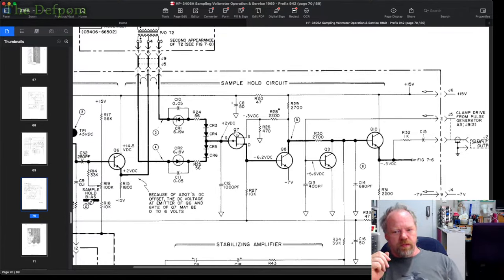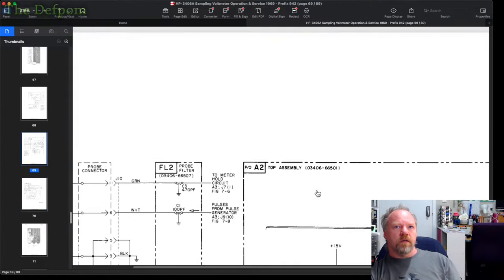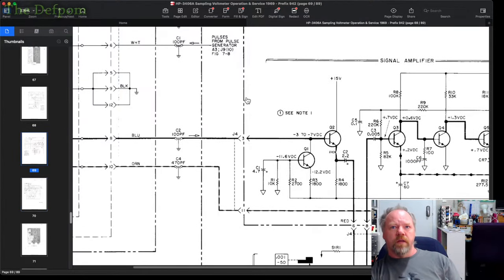What if I inject voltage into the input, see if the other voltages are correct? Well, I've tried injecting signals and checked for meter deflection when I was getting a low reading on that 0.03 volt range. And it wasn't changing anything, really. So I've tried unplugging the probe, so the probe's not even connected. And then I get, let's go to this diagram here. So this is disconnected here, so there's no probe connection.